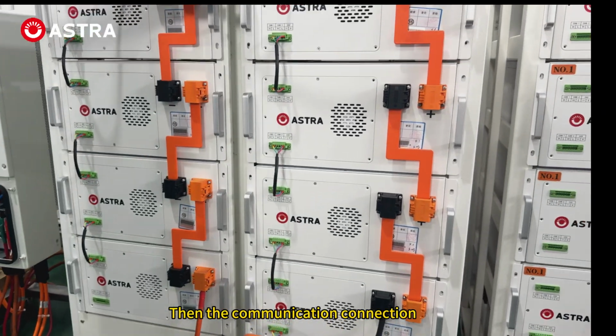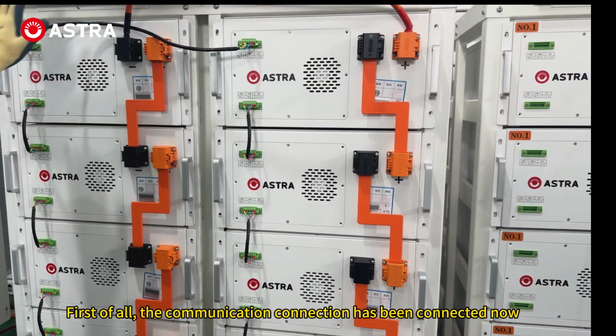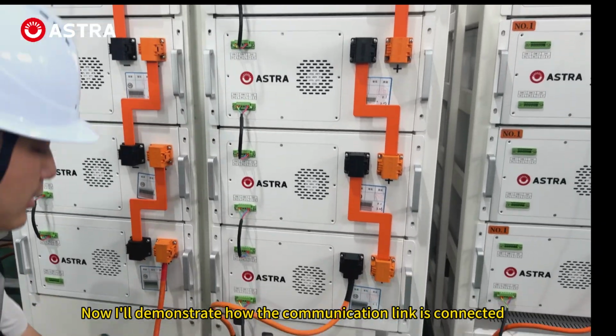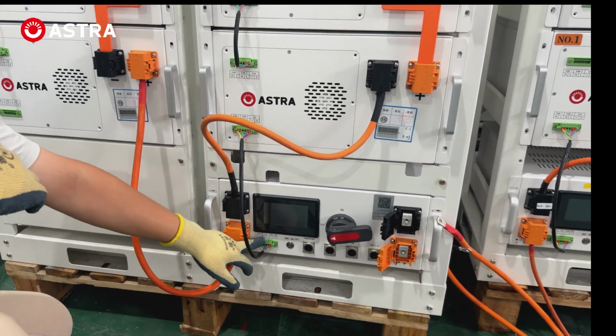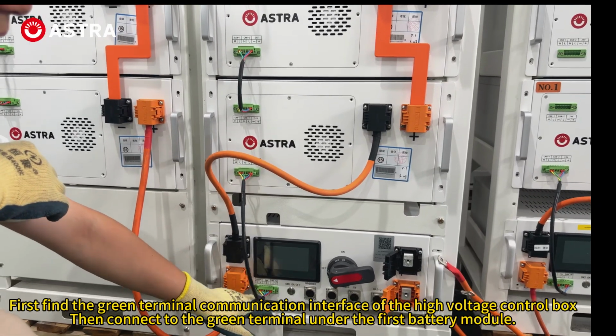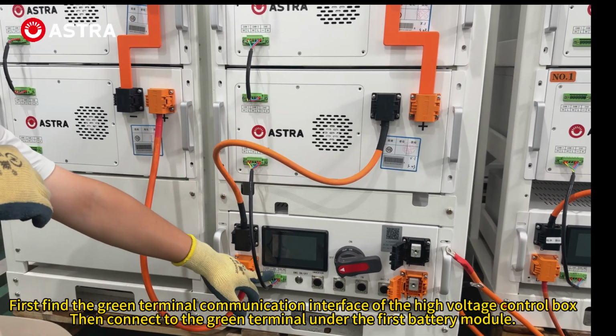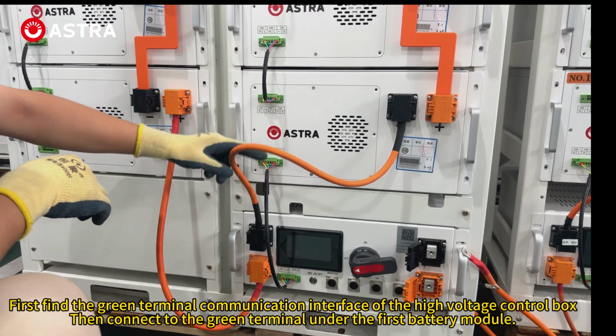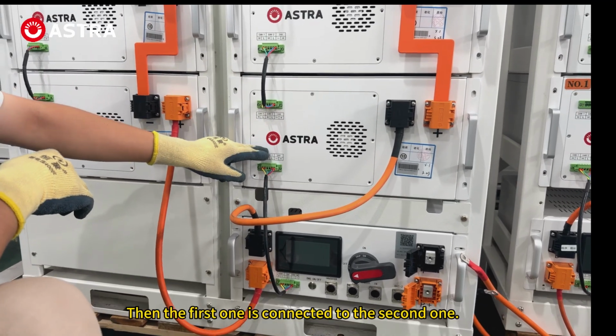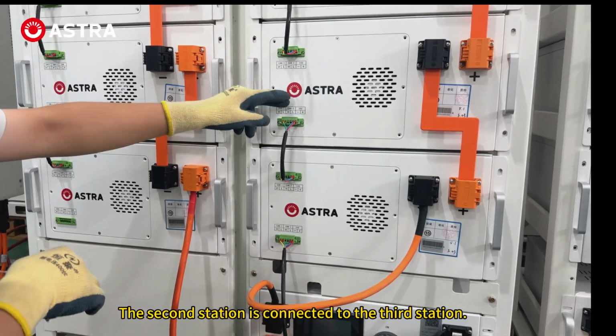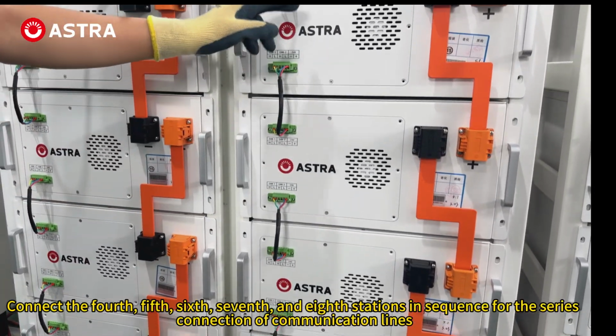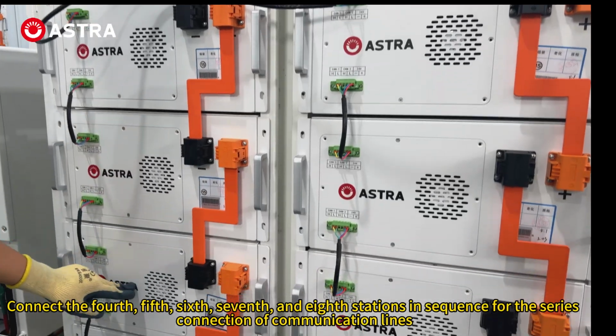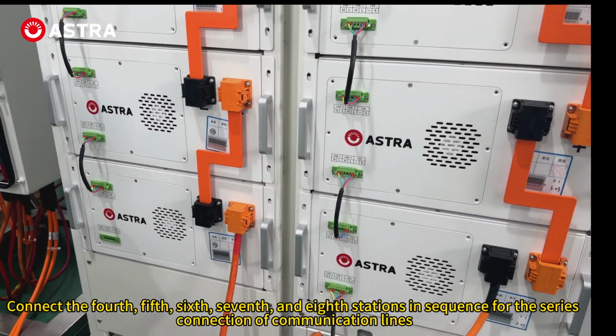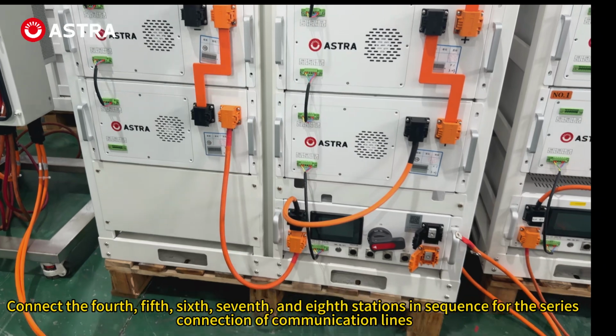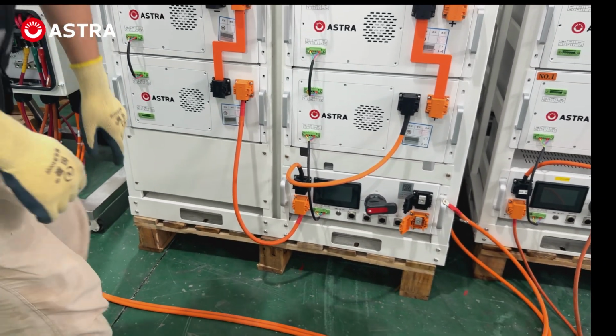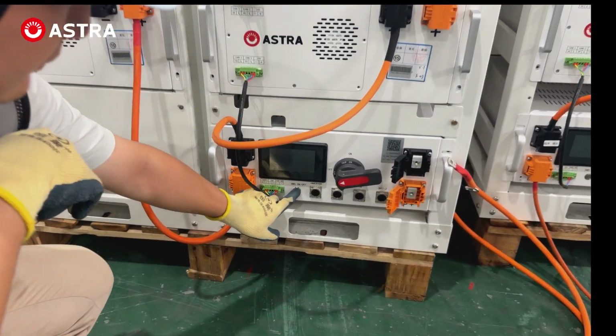Then the communication connection. Now I'll demonstrate how the communication link is connected. First, find the green terminal communication interface of the high voltage control box, then connect to the green terminal under the first battery module. Then the first one is connected to the second one. The second is connected to the third. Connect the fourth, fifth, sixth, seventh, and eighth in sequence for the series connection of communication lines. The communication part has also been connected successfully.